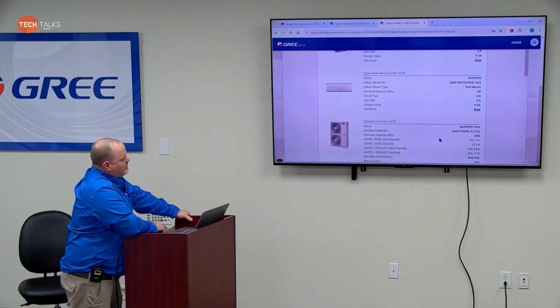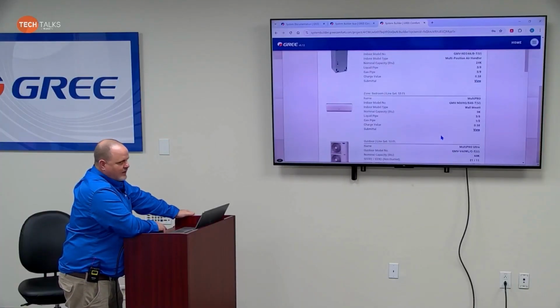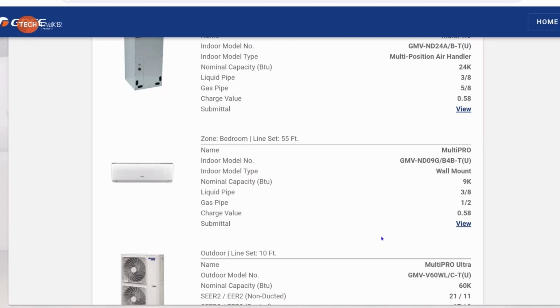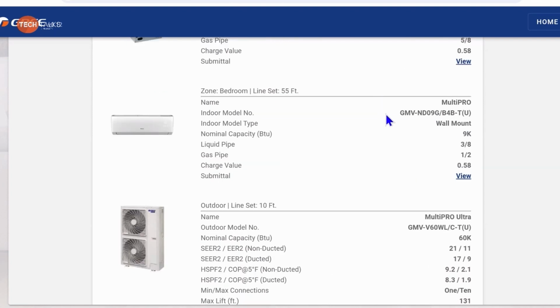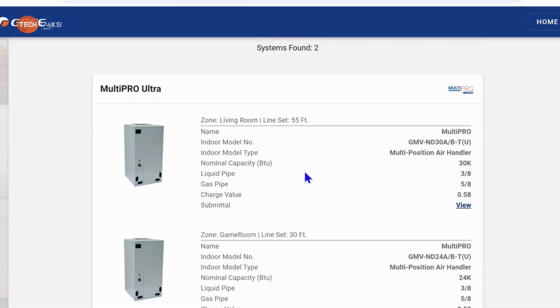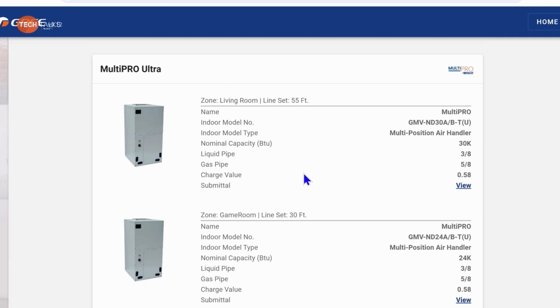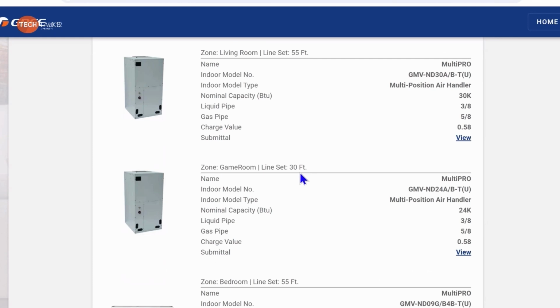This is one of those examples where I would tell you to use multiple Ys or relocate the header to keep it under 49 feet on these smaller BTU units like this 9K wall mount, so that you keep your line set sizes the same as the indoor unit and don't have to reduce back down at the indoor unit. It just adds to the ease of the installation is what I'm getting at. You can do it, there's nothing wrong with it. I'm just telling you, you're going to save yourself a lot of headache if you go to multiple Ys, or if you go to moving that header so that you stay under the 49 feet or under 50 feet.